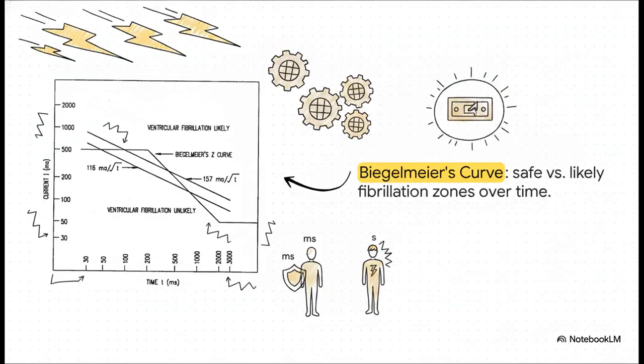Which brings us to Biegelmeier's Z-curve. This curve visually proves that survival is mostly a race against time. Notice how, as the duration of the shock decreases, the amount of current a human can tolerate before fibrillating goes drastically up. If those primary relays and circuit breakers we discussed earlier clear the fault in just a few milliseconds, a worker standing in that substation can survive a significantly higher voltage spike than if it took a full second to clear. Speed is quite literally a lifesaver here.